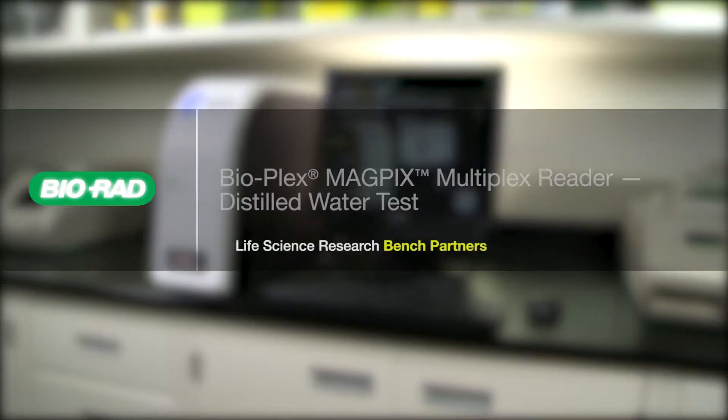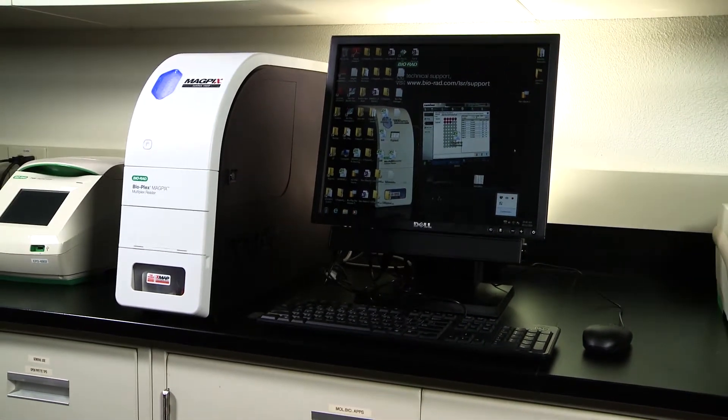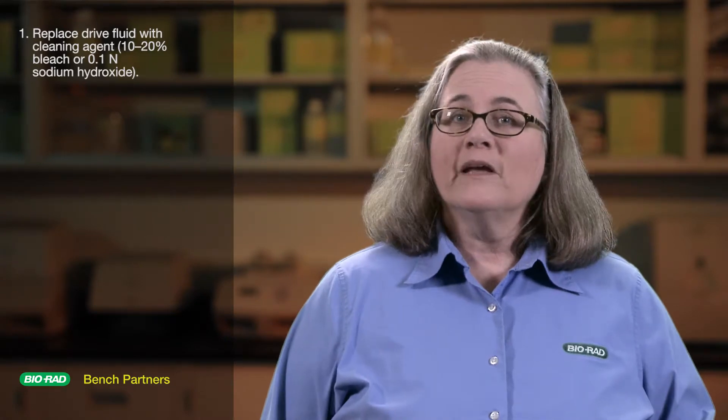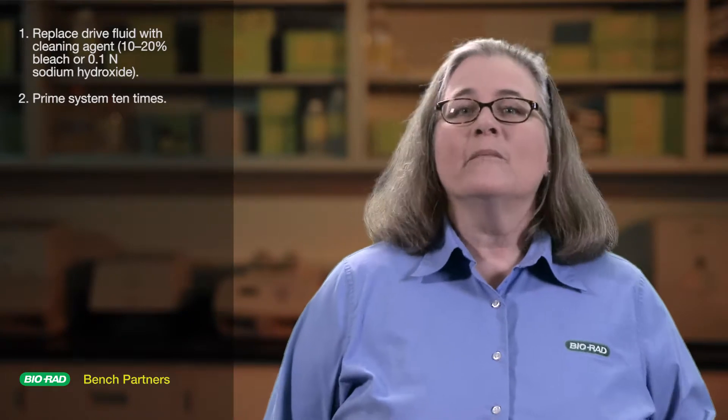Then perform the DI water test to see if the chamber is clean. Details about this test can be found in the BioPlex MAGPIX multiplex reader distilled water test video available on the BioRad Life Sciences YouTube channel. If the chamber is still clogged with beads after you've carried out these steps, an extended cleaning might be necessary. This will involve replacing the drive fluid with a cleaning agent such as 10 to 20% bleach or 0.1 normal sodium hydroxide and priming the system 10 times.